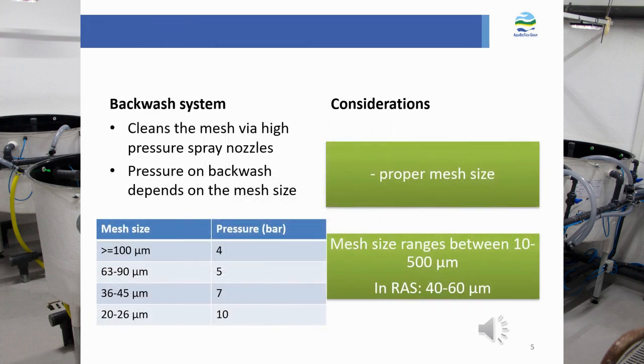The backwash system cleans the mesh via pressurized spray nozzles. The pump pressure should be selected according to mesh size: mesh larger than 100 microns requires around 4 bar; 63–90 micron mesh requires around 5 bar; 36–45 micron mesh needs around 7 bar; and the fine 20–26 micron mesh requires at least 10 bar. Mesh sizes range between 10 and 500 micrometers, but the most commonly used in aquaculture is between 40 and 60 micrometers.